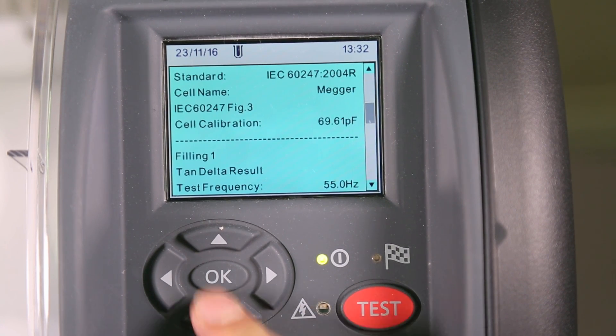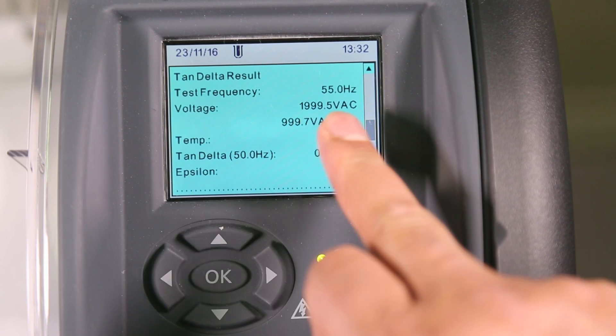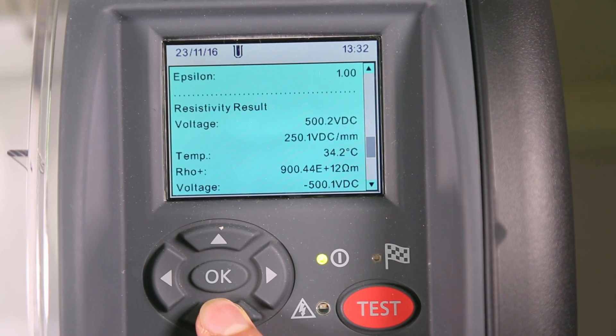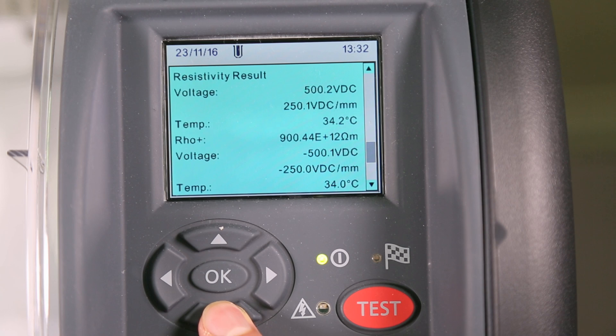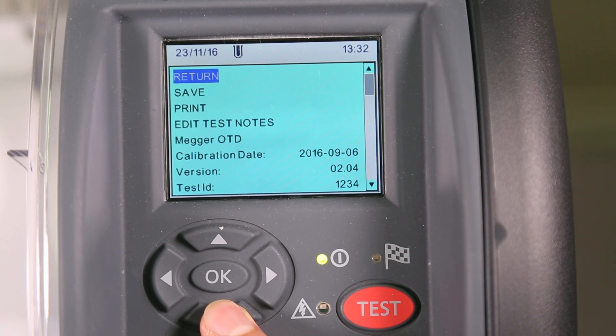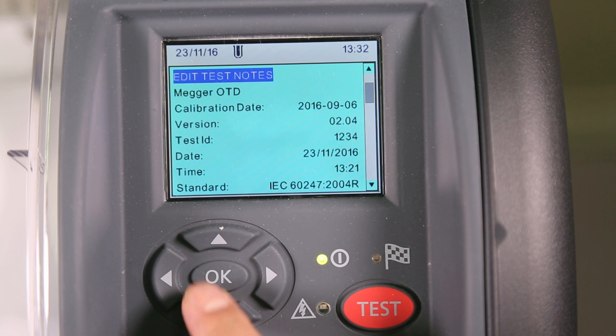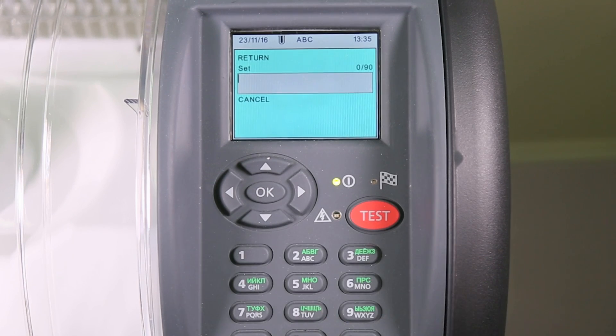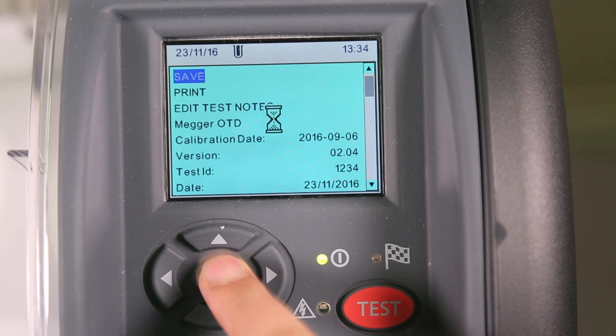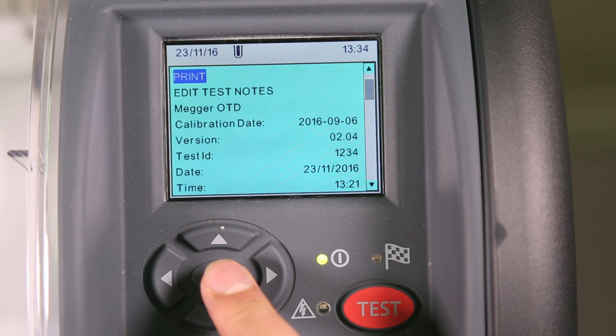When the test is complete, you can see the TAN delta results and the resistivity results on screen. From here you can save, print, or edit test notes. Select edit test notes to input any necessary notes. You can then save and print.